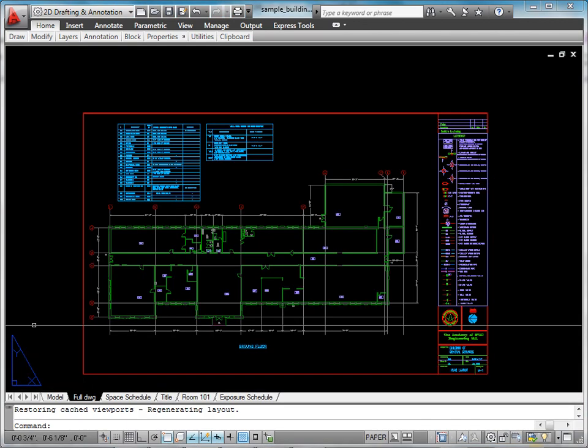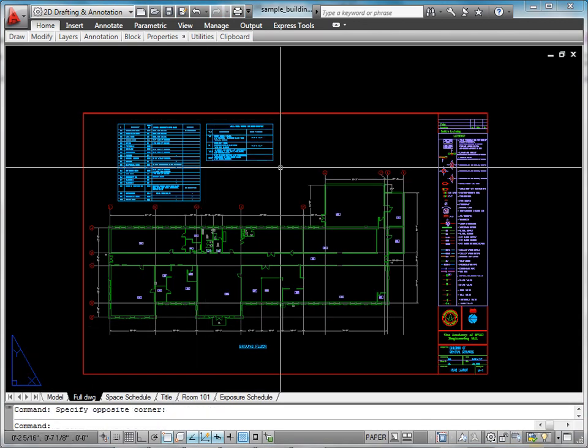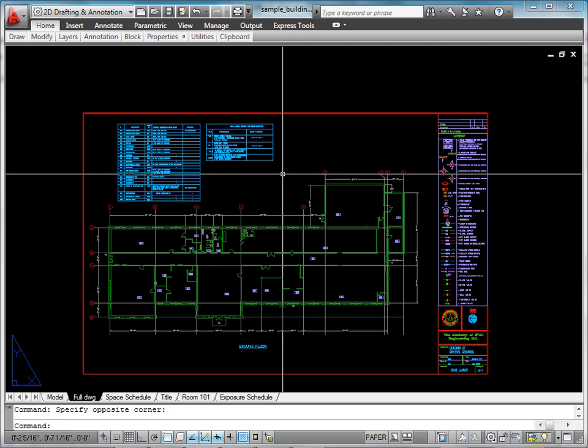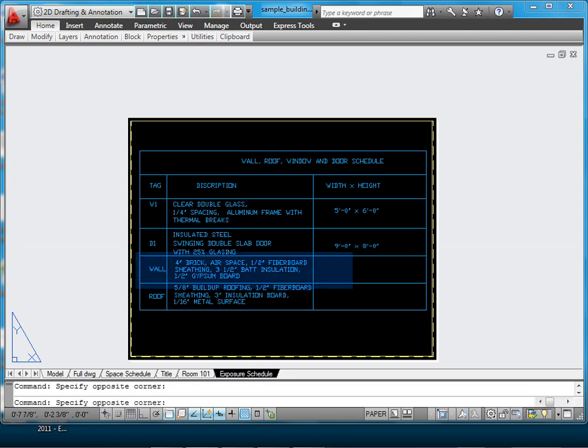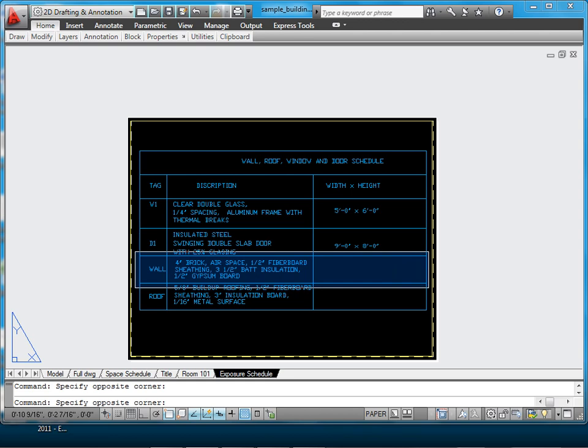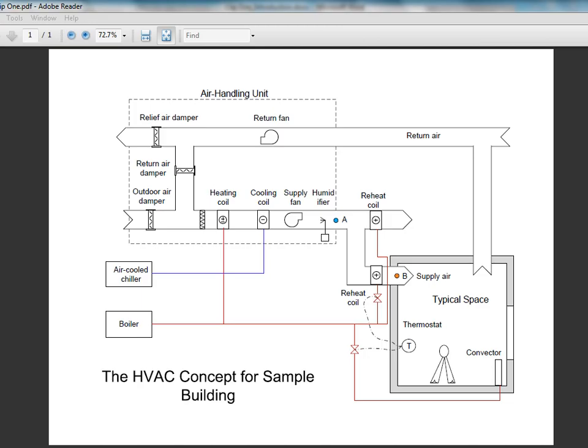The other schedule in the drawing outlines the exterior wall, roof, window, and entrance door arrangements. For example, the exterior wall includes 5 layers: a 4-inch brick, an air space, a 1/2-inch fiberboard sheathing, a 3-and-1/2-inch batt insulation, and a 1/2-inch gypsum board. This information will be required for the calculation of heat transmission through the exposures.